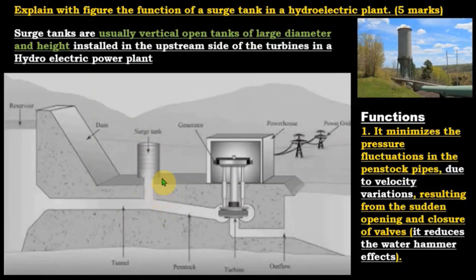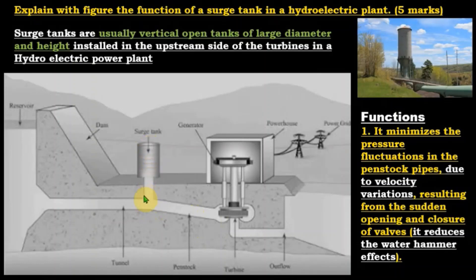What does the surge tank do? The surge tank absorbs pressure variations. For example, consider the sudden closure of a valve — the pipeline flow is subjected to deceleration, the momentum is destroyed, and automatically that excess water flows into the surge tank. This dampens out the pressure waves formed in the pipeline due to sudden velocity variations from sudden closure and opening of valves.